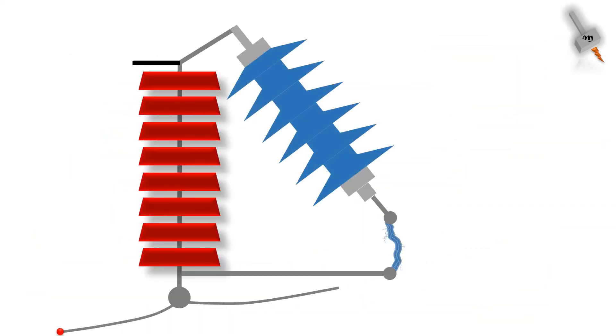When a travelling wave reaches the tower with an EGLA, the gap senses the voltage. Depending on the gap setting, a flashover happens on the spark gap which eventually converts to an arc. The zinc oxide blocks in the SBU conducts immediately and transfers the surge to the ground. As the surge energy is depleted, the SBU unit limits the follow-on current and the arc in the spark gap interrupts and the current flow ends.